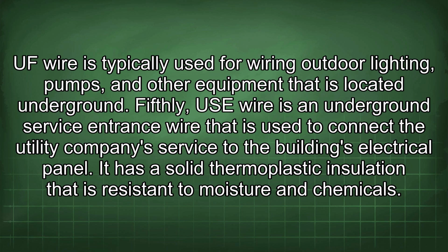Fifthly, USE wire is an underground service entrance wire that is used to connect the utility company's service to the building's electrical panel. It has a solid thermoplastic insulation that is resistant to moisture and chemicals.